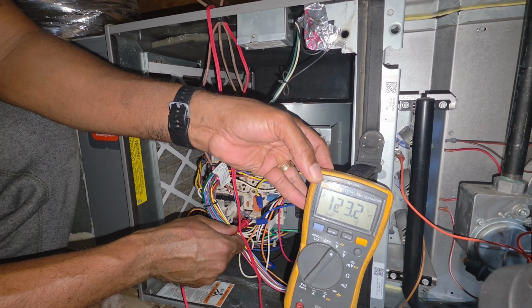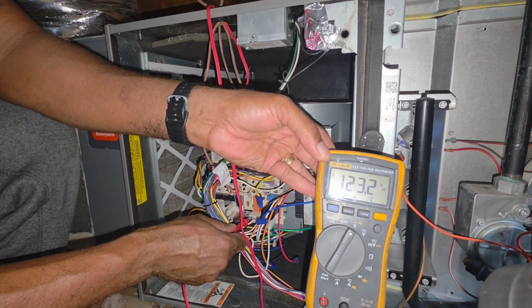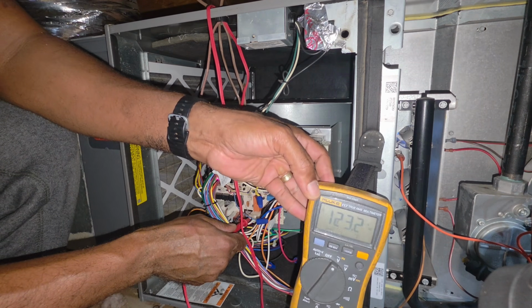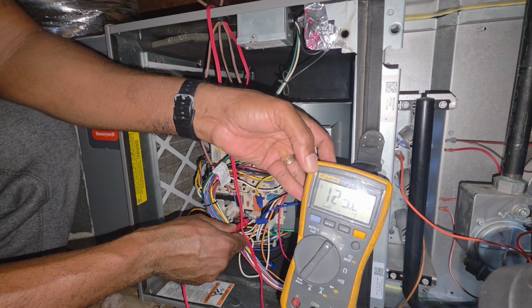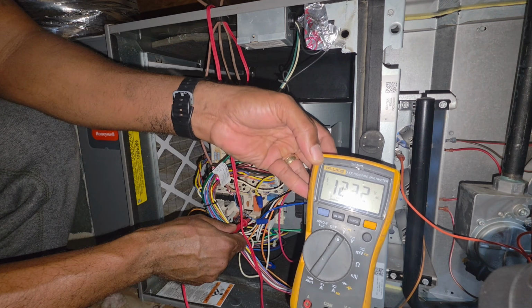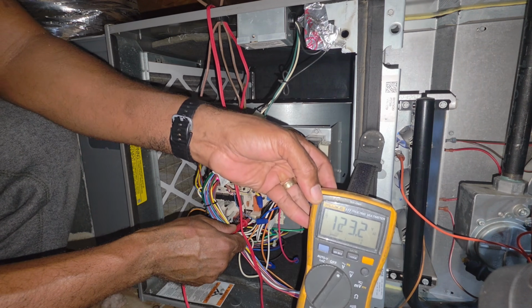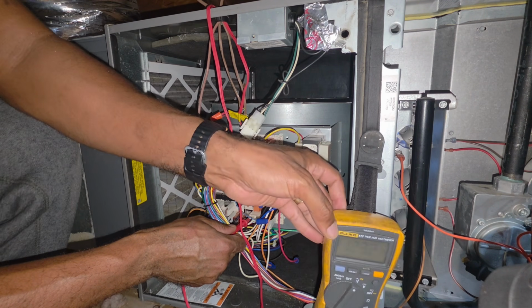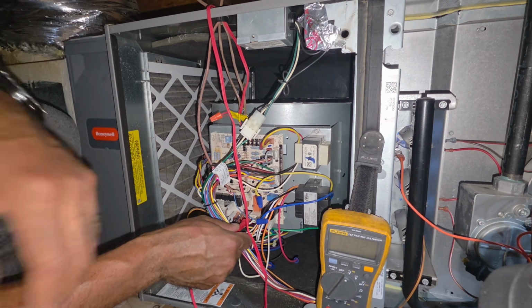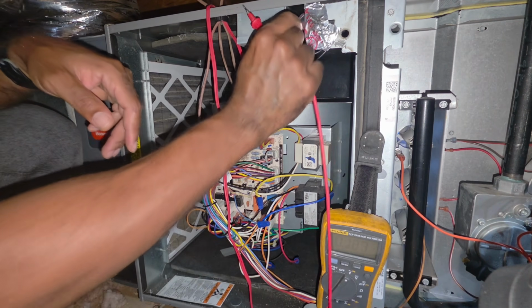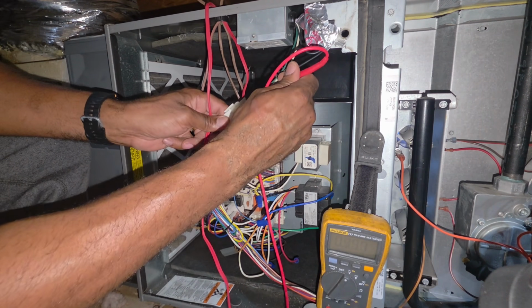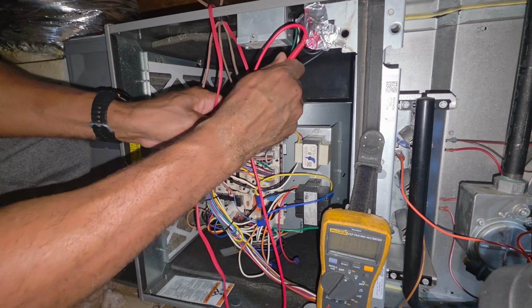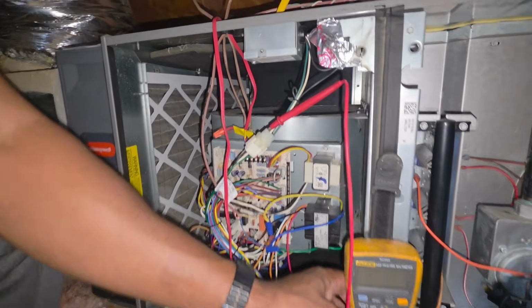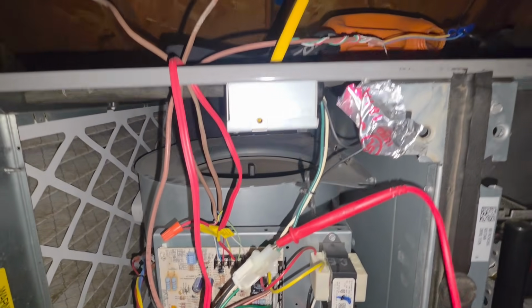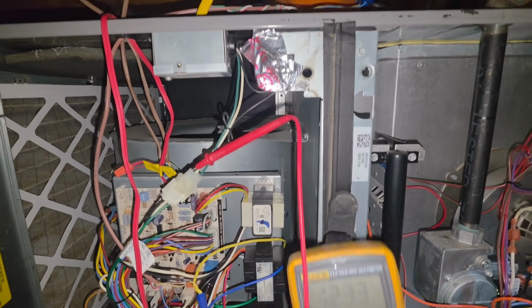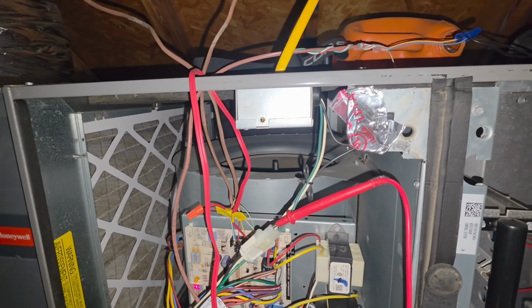So if you were troubleshooting this right here and your inducer motor is not turning on, and you were getting 0, you need to investigate that inducer motor. You need to find out if you don't have 120 going to it, if it's the control board or what's going on. If you got 120 and that inducer is not spinning, you may have a bad inducer motor. Let's see this door switch right here. Go to the black on that door switch and see what I'm getting. See my door switch? Getting 120. That just lets me know my door switch is good.